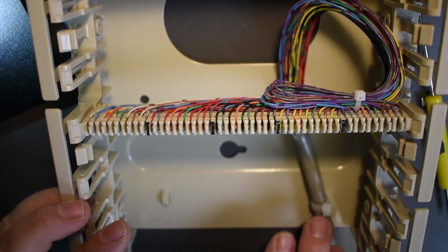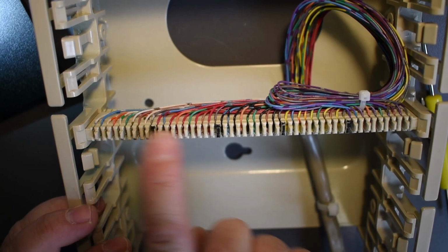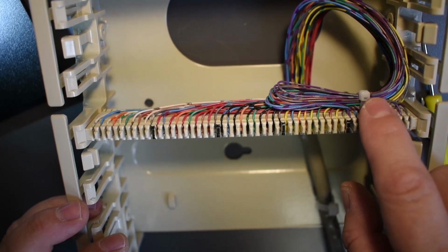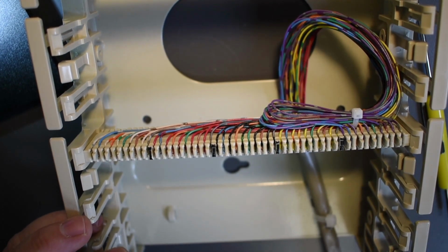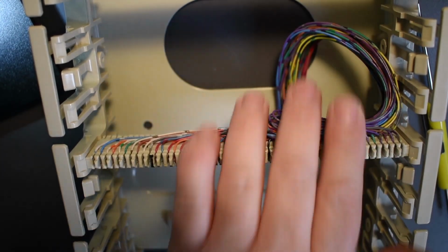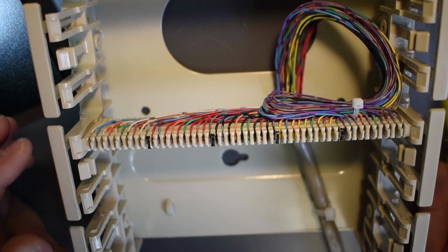I want to see, again, zip tie, nice jacket here, and I want to see that nicely punched, and nicely bound, and a nice and beautiful slack. You should be able to just push that jacketing over, and that should be able to cover that. No mess here, please, no mess. Okay, you got mess, you get marks deducted. So that's the first picture.